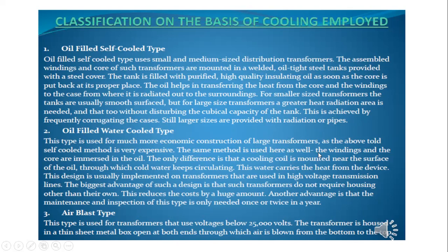The same method is used here: the windings and core are immersed in the oil. The only difference is that a cooling coil is mounted near the surface of the oil. So there is one difference between the oil-filled self-cooled and the oil-filled water-cooled type: the cooling coil is mounted near the surface of the oil, through which cold water keeps circulating.